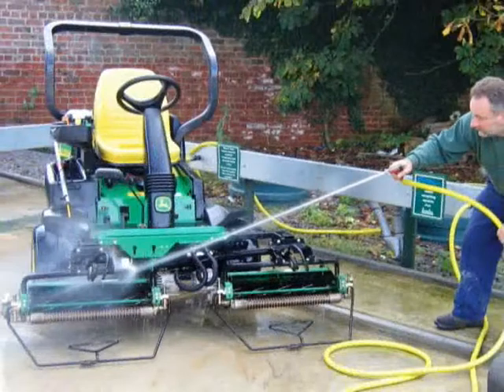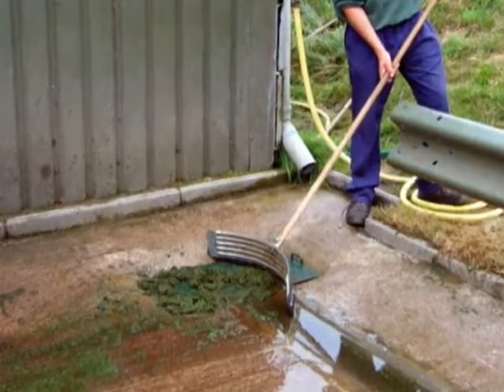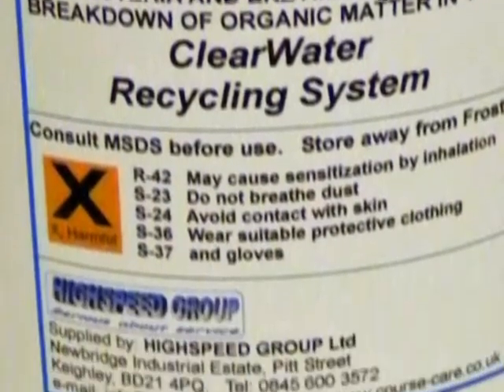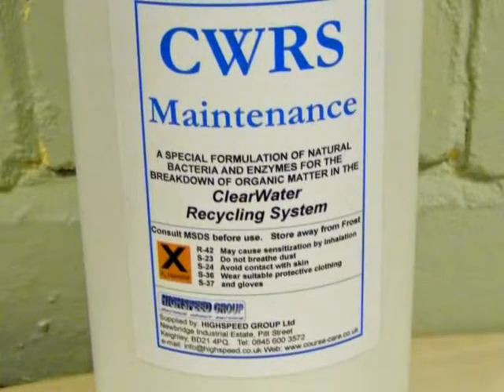So how does it all work? Contaminated wash-water flows from the purpose-built wash-pad through a primary filter and grass-trap and sand filter, both of which remove most solid matter, then enters the underground tank. Microorganisms break down the effluent in the oxygen-rich environment, producing clean water and carbon dioxide. Water passes through a large coalescing filter to the secondary storage for settling of any suspended solids that remain in the Clearwater.